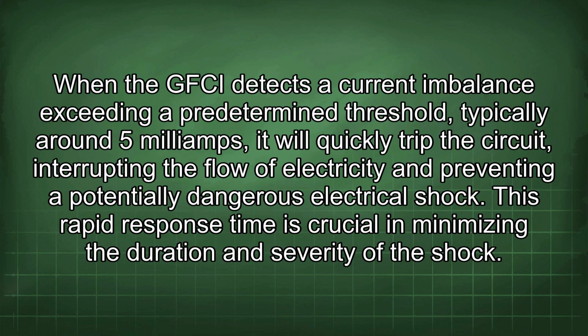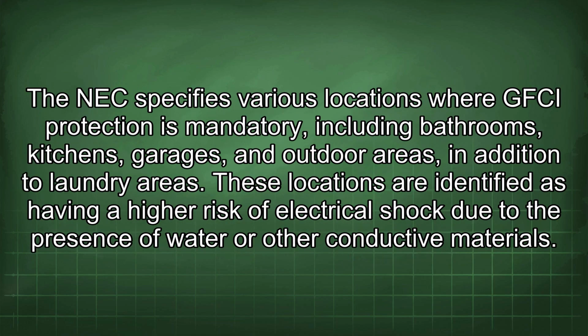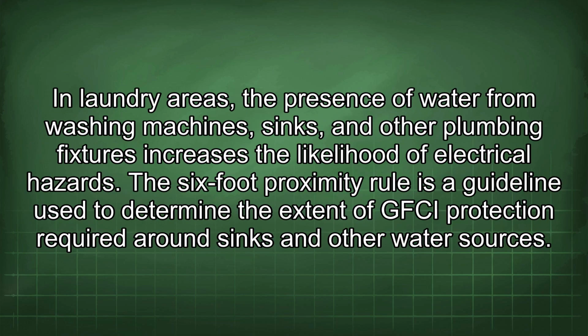When the GFCI detects a current imbalance exceeding a predetermined threshold, typically around 5 mA, it will quickly trip the circuit, interrupting the flow of electricity and preventing a potentially dangerous electrical shock. This rapid response time is crucial in minimizing the duration and severity of the shock. The NEC specifies various locations where GFCI protection is mandatory, including bathrooms, kitchens, garages, and outdoor areas, in addition to laundry areas. These locations are identified as having a higher risk of electrical shock due to the presence of water or other conductive materials. In laundry areas, the presence of water from washing machines, sinks, and other plumbing fixtures increases the likelihood of electrical hazards.